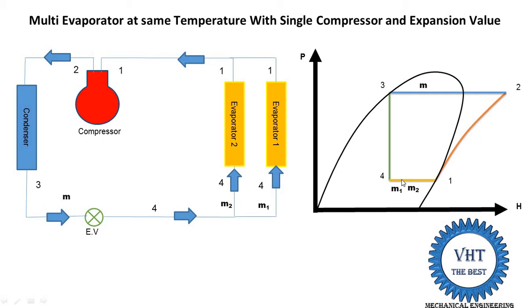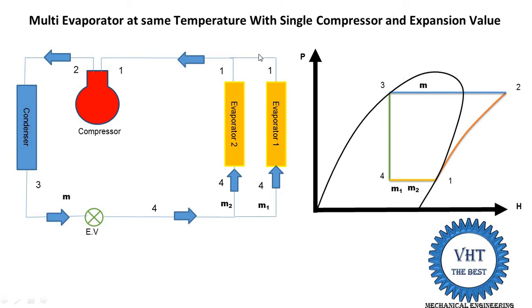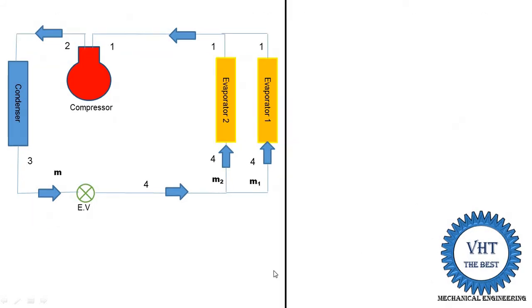The schematic diagram and P-h diagram are now drawn for the system. Next we find out the equations for COP. Using the schematic diagram as reference: m1 is the mass of refrigerant circulated in evaporator 1, m2 in evaporator 2, and m equals m1 plus m2. From the P-h diagram, draw vertical lines from each numbered point and read the enthalpy values h1, h2, h3, h4.